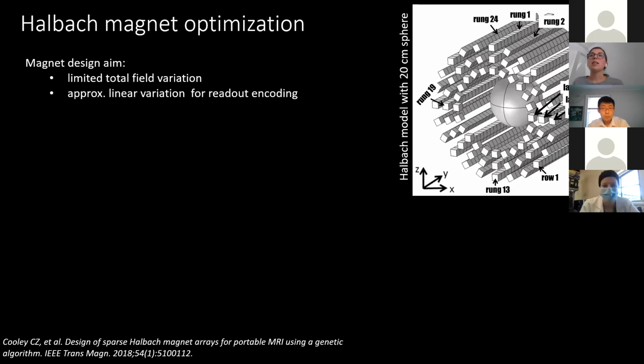To actually design the magnet, we set up an optimization problem with the aim of limiting the total field variation, because it's difficult to excite and measure the MR signal if you have too much field variation in the field of view. So we aim to limit the total field variation, but at the same time we wanted to create a linear, limited field variation in the field of view to do the readout and image encoding.